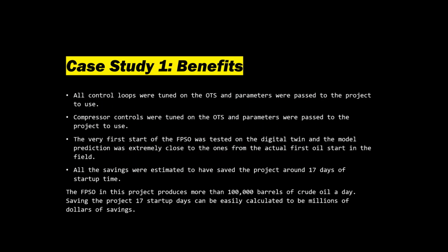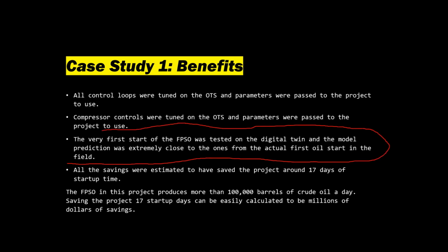All control loops were tuned between the OTS and the real project. Compressor controls were tuned similarly. The first start of the FPSO was tested with the digital twin, and model prediction was extremely close to the one from the actual first oil start, which is excellent because when you want to experiment with your yield, you can do it with the digital twin before you deploy to the real plant.